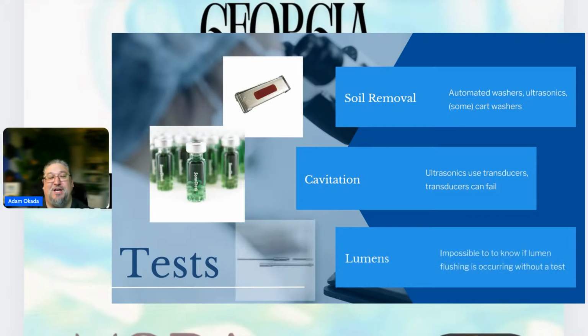Lumen flushing is another function people often aren't testing. We hook up laparoscopics, robotics, and all kinds of instruments to our lumen flushing function, but we're not testing it. You could have a kinked hose, a separation, or a broken O-ring. Those pumps that supply water to the lumen flushing are often a separate mechanism. We went into a hospital where one of the pumps was turned off, so all the flushing on one side of the ultrasonic wasn't happening—and there's no way to know that unless you have a test for lumen flushing functionality.